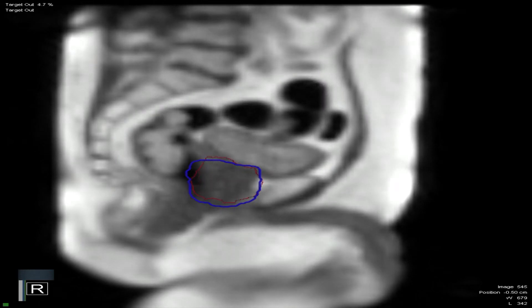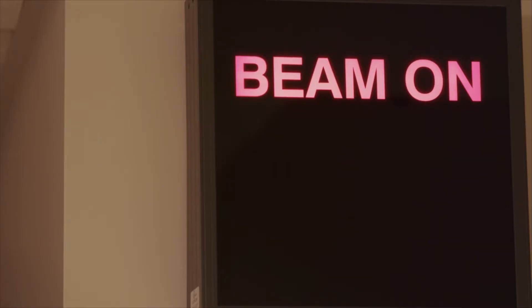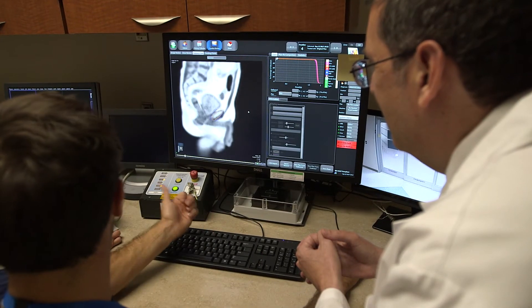The ViewRay unit knew about it and automatically paused the radiation beam right when that was happening. The gas bubble passed, the prostate moved back into position, and the beam turned back on.